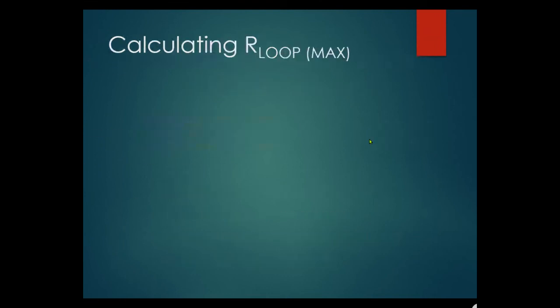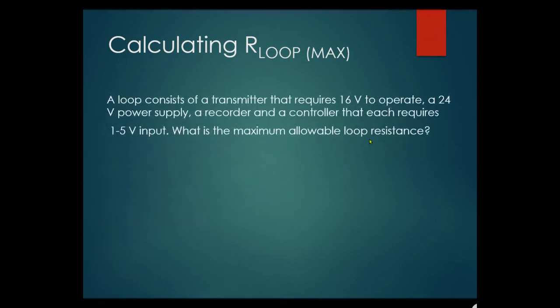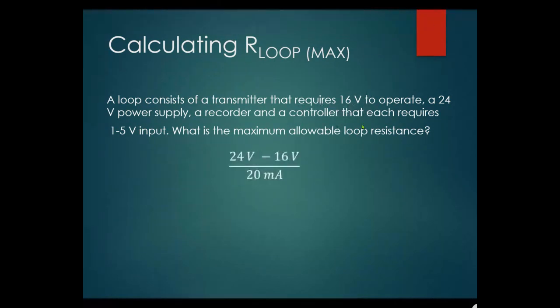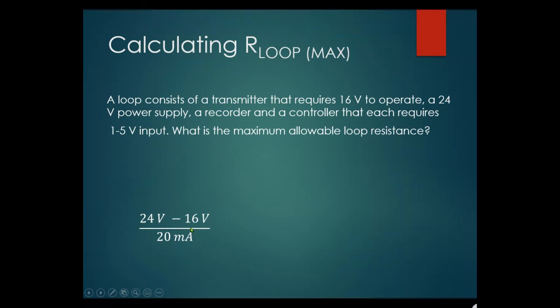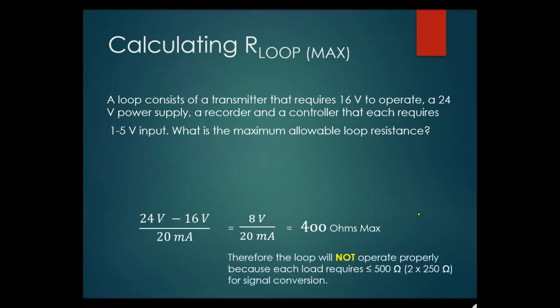The 20mA is the upper range current value. Example: a loop has a transmitter requiring 16 volts to operate, a 24 volt power supply, a recorder and a controller each requiring 1 to 5 volt input (each needing a 250 ohm resistor). Maximum allowable loop resistance: (24V − 16V) ÷ 0.020A = 400 ohms. Therefore the loop will not operate properly because each load requires 250 ohms — two loads equals 500 ohms, which exceeds the 400 ohm maximum.